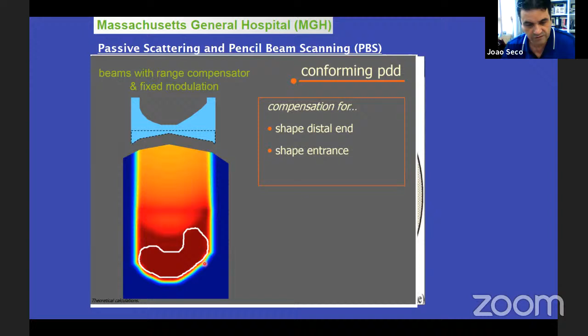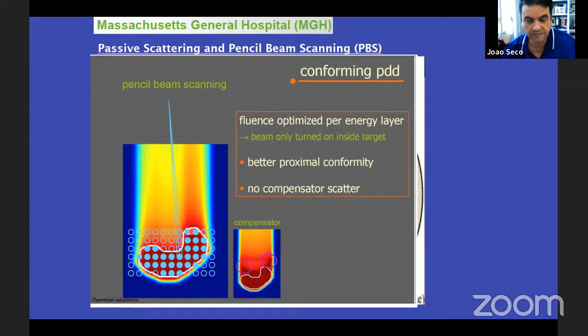So here is the passive scattering system that I would deliver. You see the horns of the problem. So you have horns here in high dose. You have good shaping in the distal area. But if I use pencil beam scanning, just overlapping now, I lose these horns, and I have shaping line by line. So now I have a beam that's scanning layer by layer and delivering to all these points. And I don't have any more of these hotspots that I would see here with the range compensator. So the passive scattering system is good for shaping the distal part, but it's poor for shaping at the entrance, while pencil beam scanning allows you to shape both the distal and proximal side. And that's the advantage. That's why people have commissioned all the new beams to be pencil beam scanning.